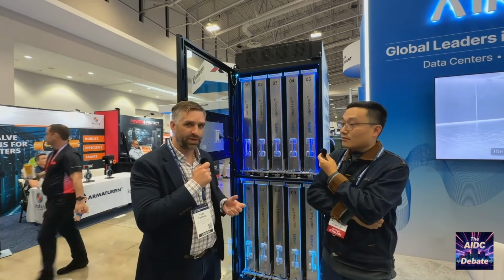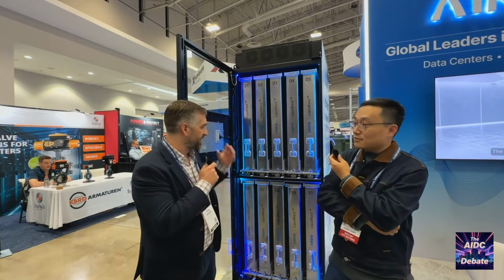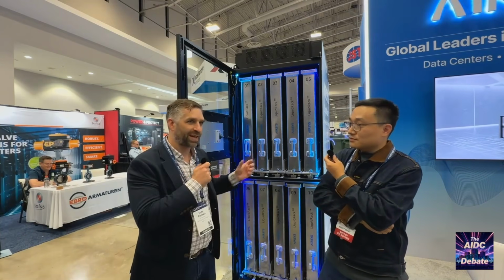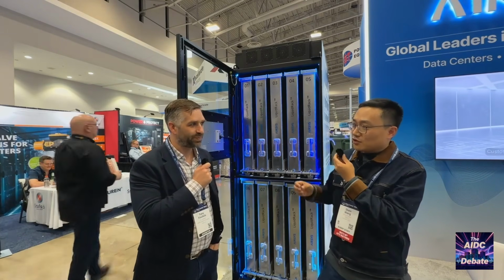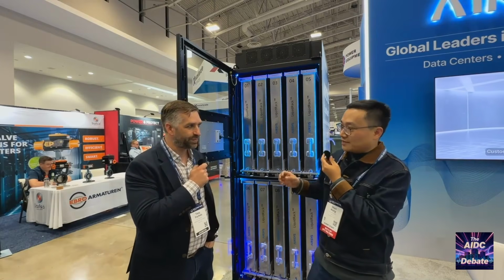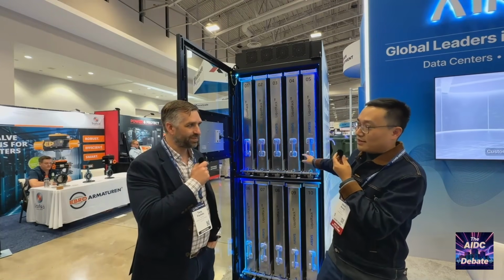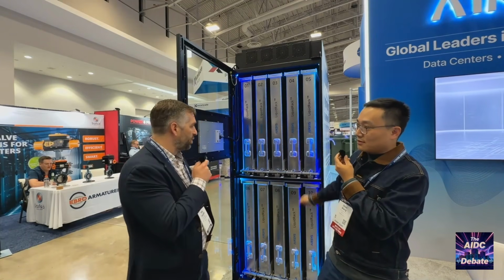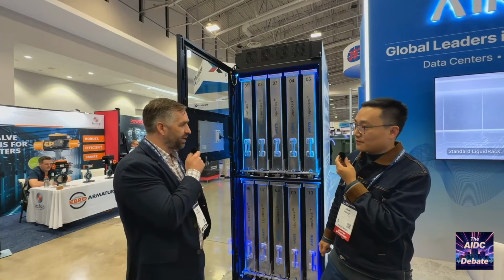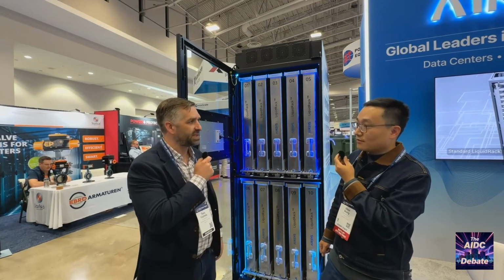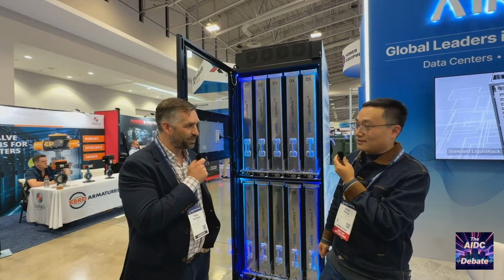You really simplify the system overall - you go from dry cooler to liquid rack, nothing in between. So if you recommend a dry cooler, that means this can handle quite high working temperatures. Yeah, we've tested it - we can bring facility water up to 60 C. Wow, that's amazing.